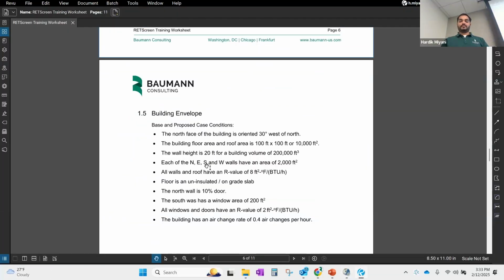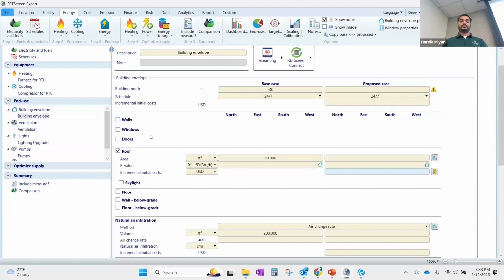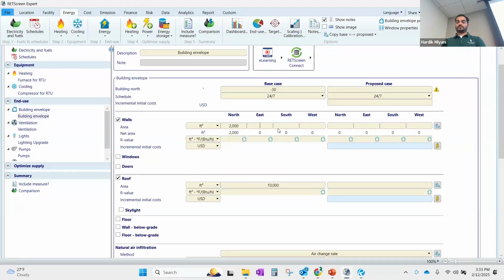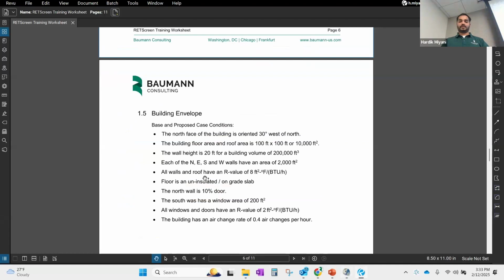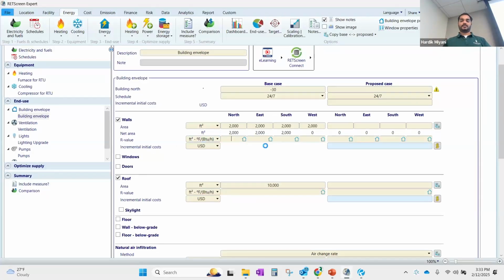So we have the volume of 200,000 cubic feet. The east, west, north, and south walls are each 2,000 square feet. My walls and roof have an R value of 8 square feet degree Fahrenheit per BTU. I'd recommend checking the units carefully since it often creates confusion. If you change the units, it will give you the U value instead. Depending on what information you have, you can enter it accordingly. The roof also has an R value of 8.